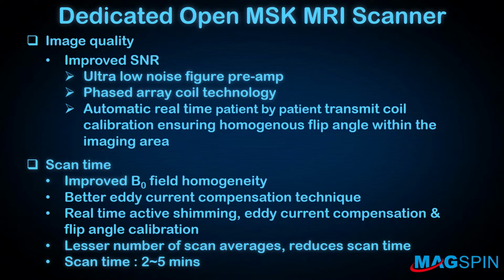And the other thing is we managed to upgrade the RF system. So compared to last time, right now we can have ultra low noise preamps. And also we can use phased array coils. And also right now we have the auto calibrations for the transmit coils so as to ensure the flip angles within the imaging areas are always homogeneous, within 5%.